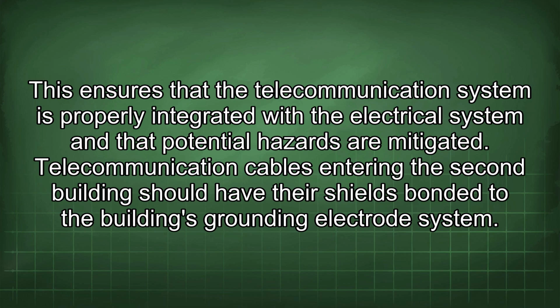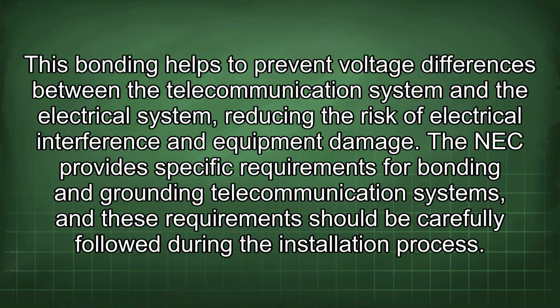This ensures that the telecommunications system is properly integrated with the electrical system and that potential hazards are mitigated. Telecommunication cables entering the second building should have their shields bonded to the building's grounding electrode system. This bonding helps to prevent voltage differences between the telecommunication system and the electrical system, reducing the risk of electrical interference and equipment damage. The NEC provides specific requirements for bonding and grounding telecommunication systems, and these requirements should be carefully followed during the installation process.